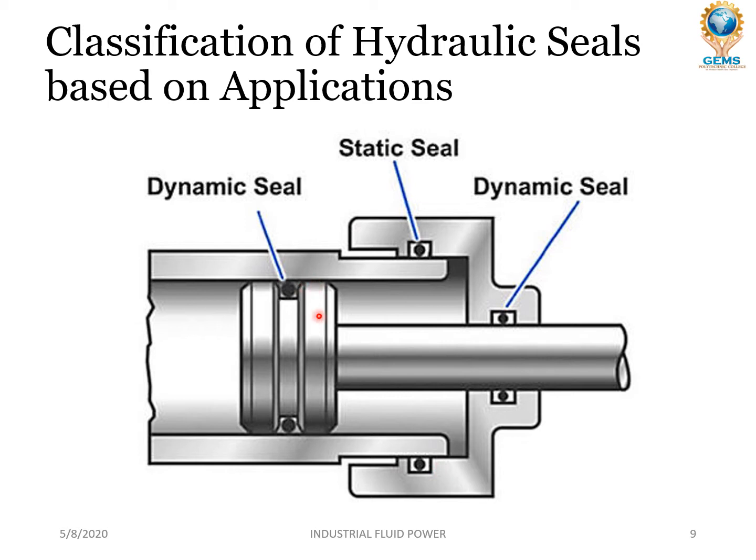But for dynamic seals, you can see in the piston head, we are using the dynamic seal which seals between the piston and the cylinder body, and this is the dynamic seal which is used in the base and the piston rod. So dynamic seals are used for mating parts with relative motion. Static seals are also used for mating parts but without any relative motion.